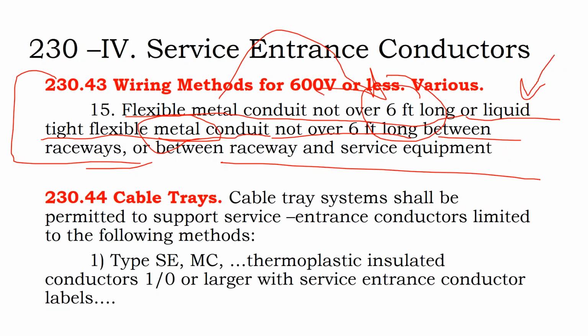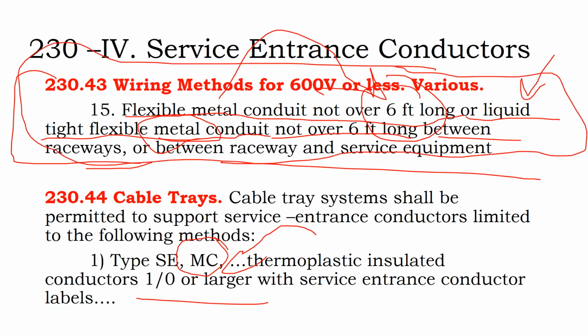Cable tray systems. We get into cable trays to support larger service entrance conductors, but there are specific cables that can only go inside these cable trays. We also have an MC cable referenced here, as we'll learn later. That's called a metal clad conductor. Since we're on the same slide, one solution, if you wanted to run flex metal conduit from the rooftop all the way down to the battery room, is to throw out the metal conduit aspect of it. We'll learn that DC wiring has to be enclosed in a metal raceway, but metal clad cable counts as a full metal enclosure, and you could just run metal clad cable straight from the roof penetration down to the battery room.